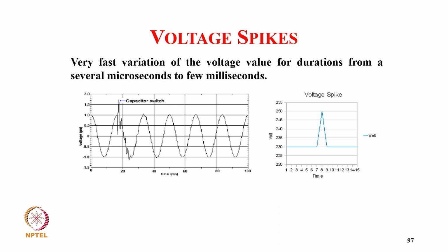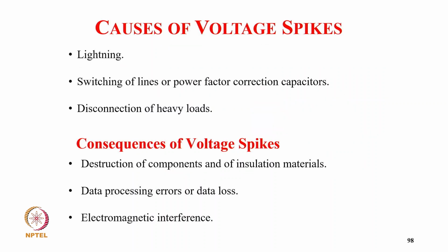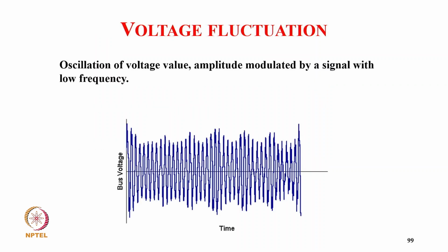So, a voltage spike is a very fast variation of the voltage value lasting for several microseconds to a few milliseconds. The causes of voltage spikes are lightning, switching of lines, power factor correction capacitors, and disconnection of heavy load. Consequences of voltage spike: destruction of components and insulation material, data processing errors and data loss, and electromagnetic interference.